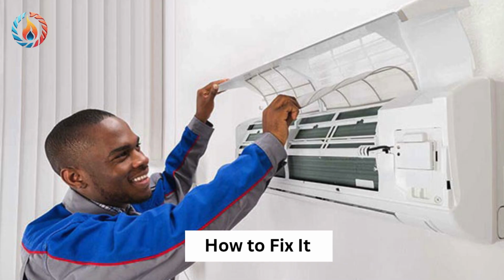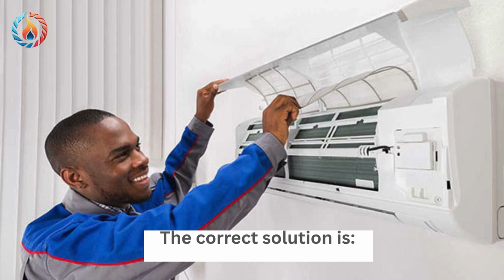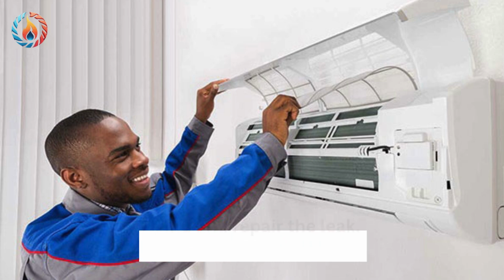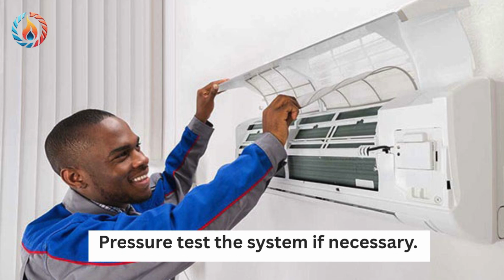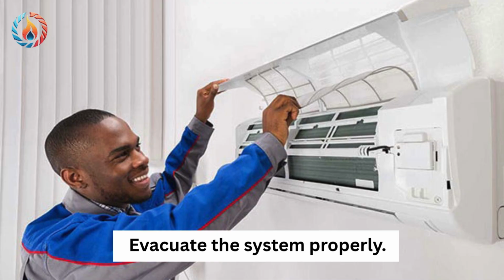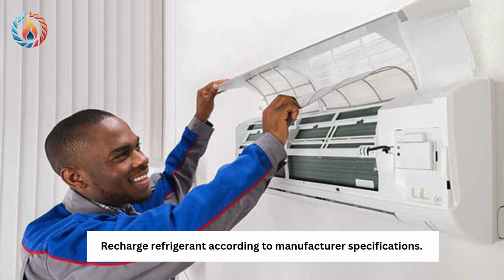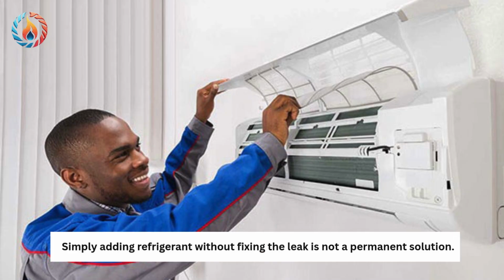How to fix it? The correct solution is, find and repair the leak. Pressure test the system if necessary. Evacuate the system properly. Recharge refrigerant according to manufacturer specifications. Simply adding refrigerant without fixing the leak is not a permanent solution.